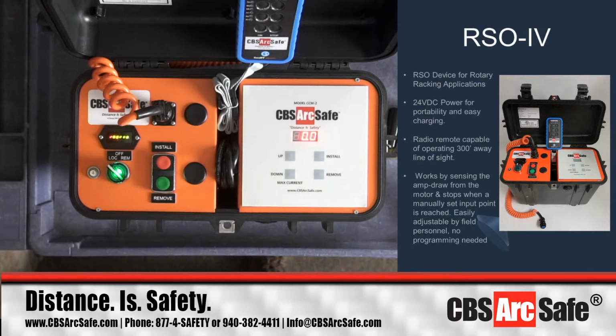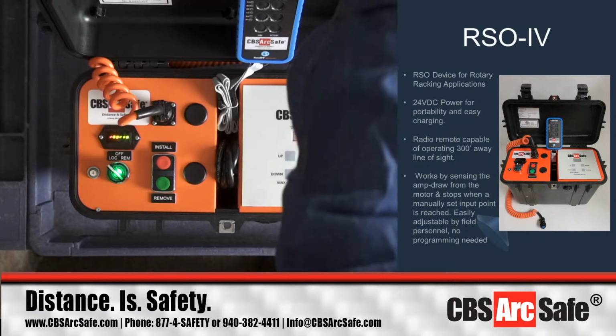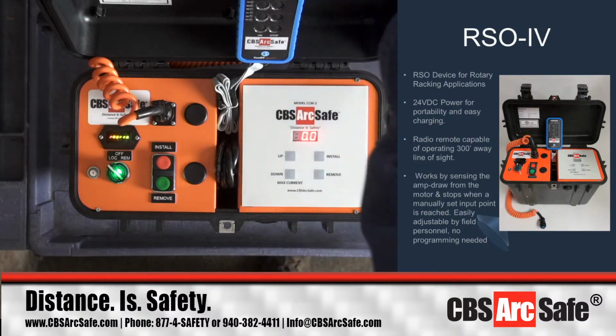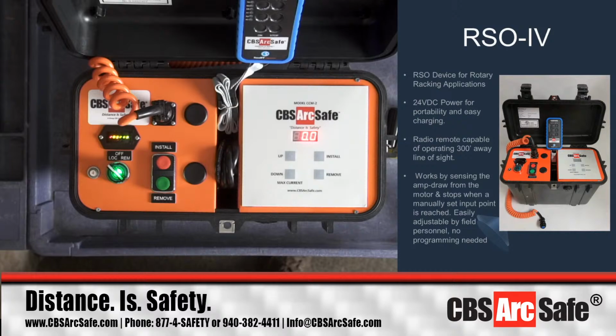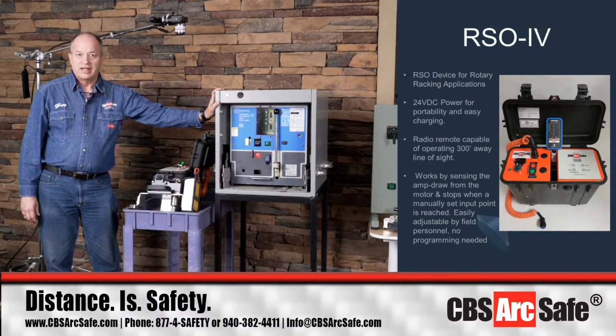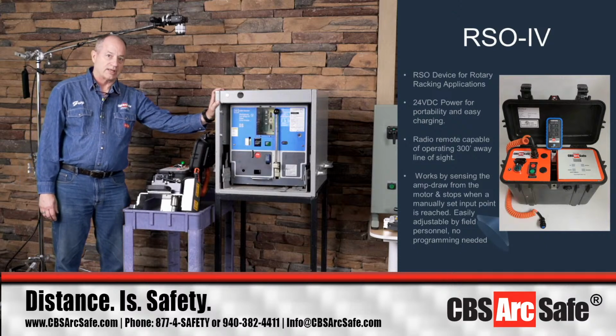We can check what our install value is, at 5.1, and our remove value at 3.4. We work to determine those values based on the breaker you're going to be operating. Until 2012, no manufacturer put it in the specifications: how much torque does it take to rack my breaker?